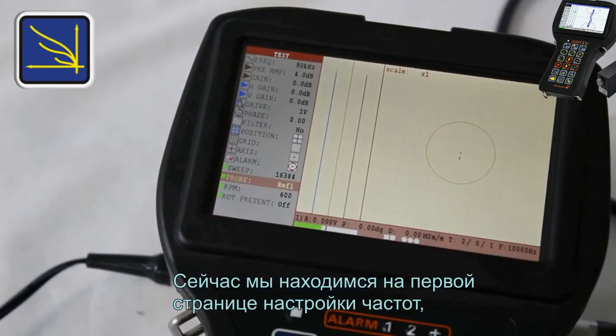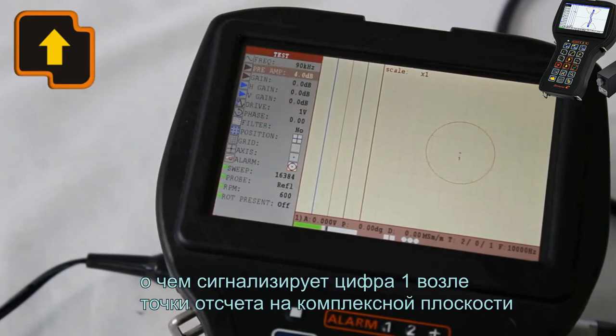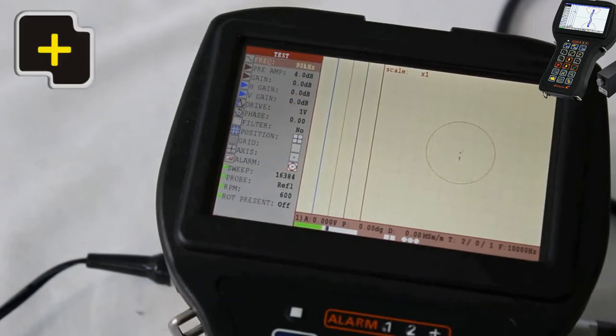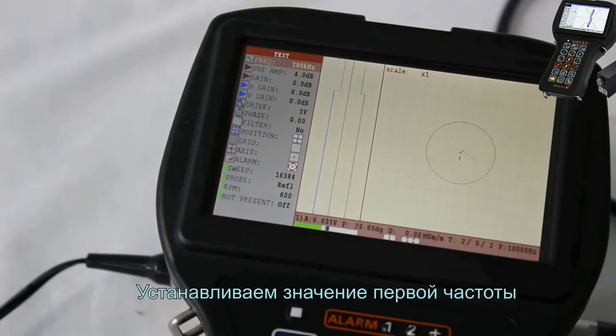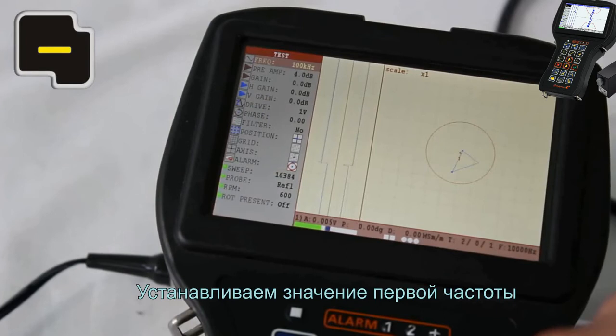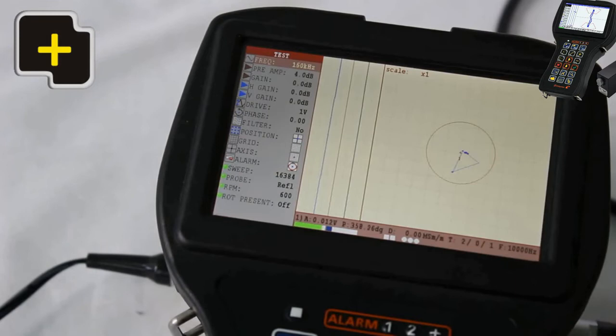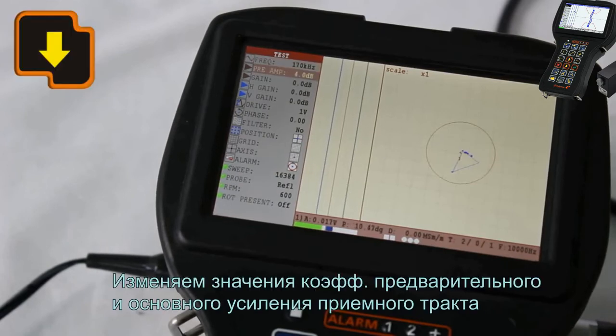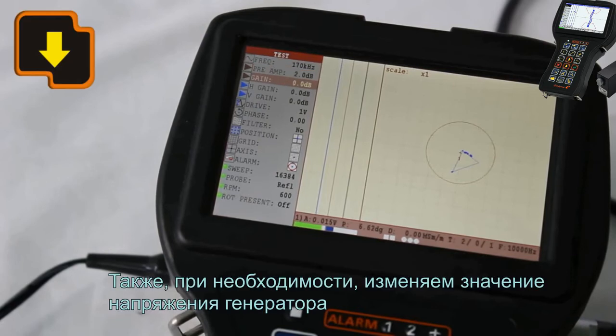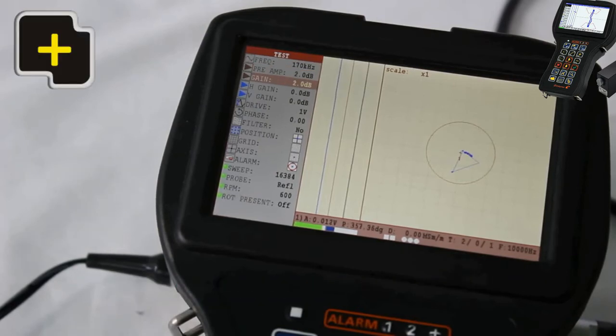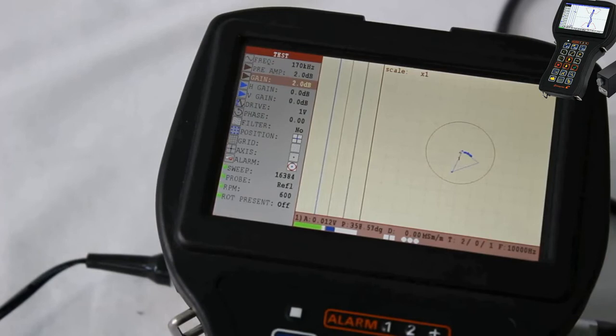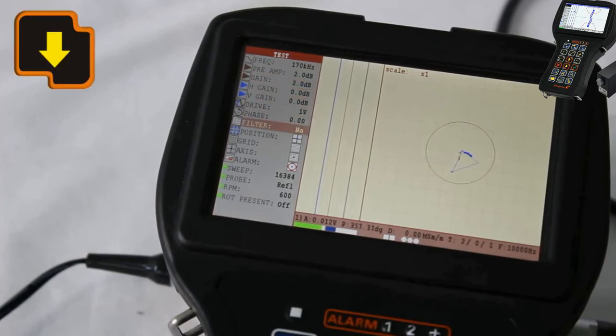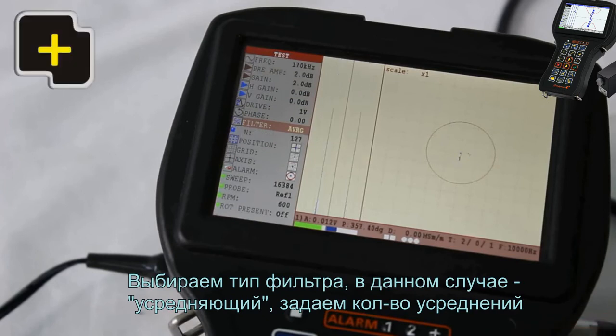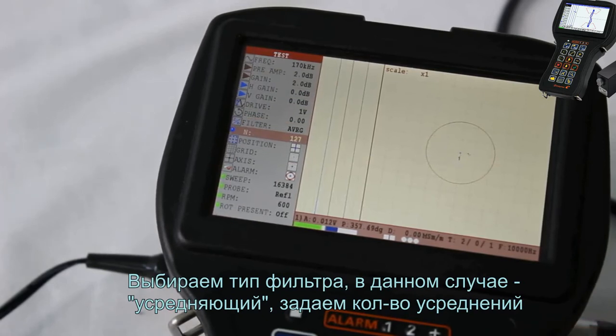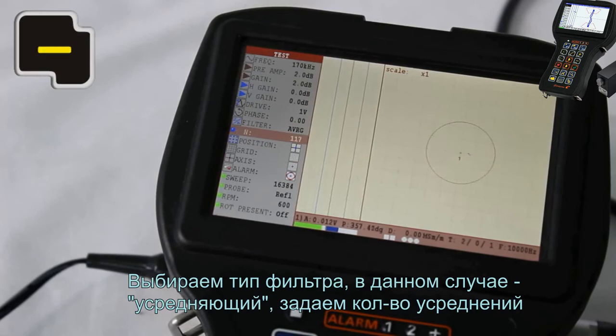Now we are located on the first page of frequency setup, that is assigned with the digit 1 located near the 0 point on a complex plane. Set up the value for the first frequency. Change the preamplifier and main gain. Also, if required, change the value of a generator voltage. Select the filter type, in our case, averaging, and set up the number of averages.